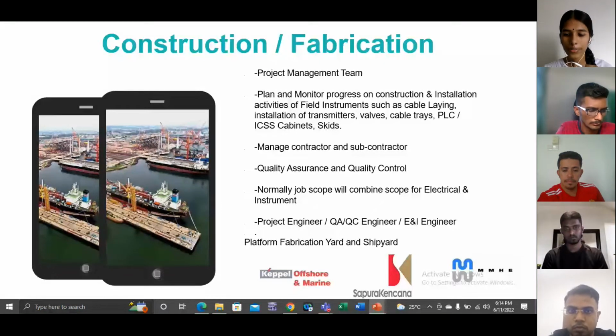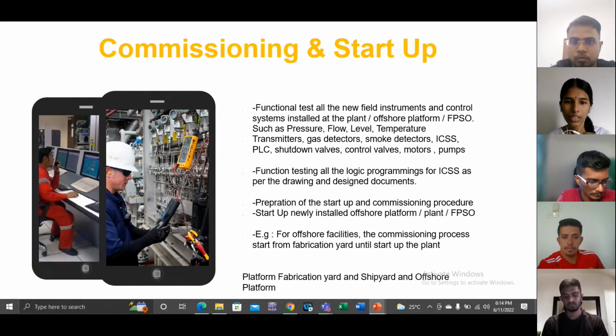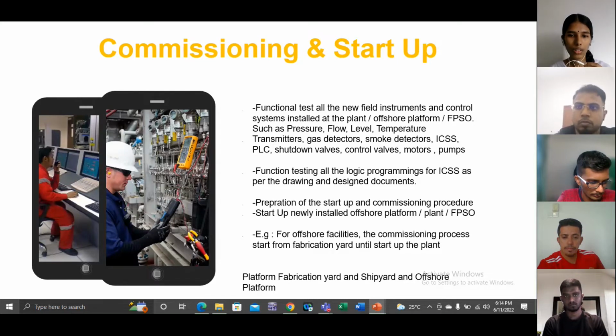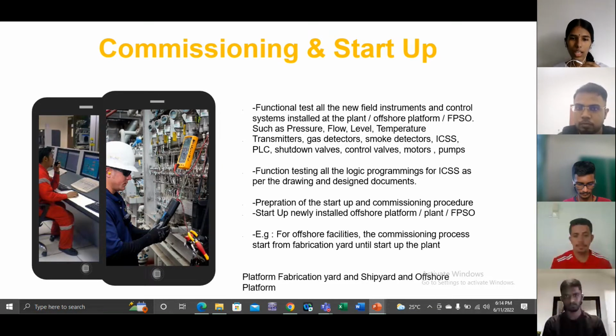Next slide is about commissioning and startup. Functional test all the new field instruments and control systems installed at the plant, for example flow, level, and temperature transmitters. Function testing all the logic programming for ICSS as per the drawing and design document. Third is preparation of the startup and commissioning procedure.